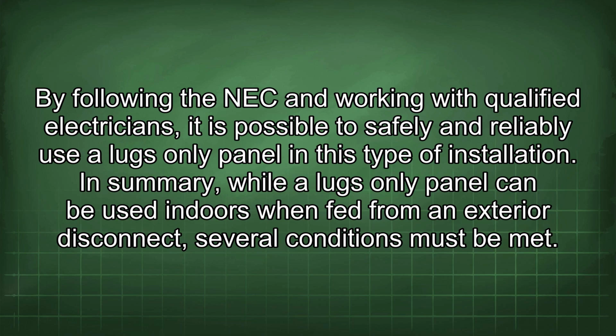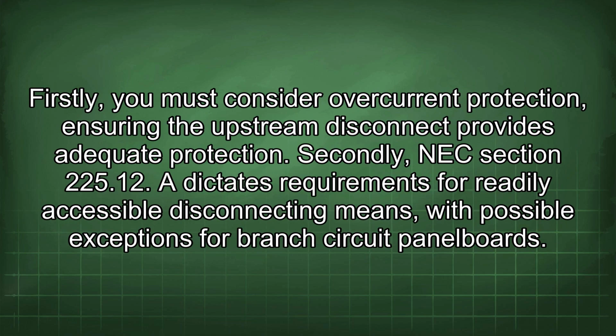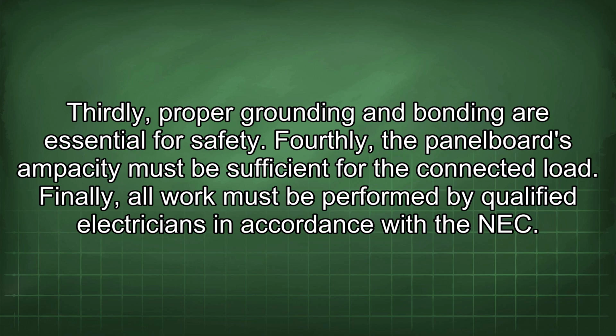In summary, while a lugs-only panel can be used indoors when fed from an exterior disconnect, several conditions must be met. Firstly, you must consider overcurrent protection, ensuring the upstream disconnect provides adequate protection. Secondly, NEC Section 225.12 dictates requirements for readily accessible disconnecting means, with possible exceptions for branch circuit panel boards. Thirdly, proper grounding and bonding are essential for safety. Fourthly, the panel board's ampacity must be sufficient for the connected load. Finally, all work must be performed by qualified electricians in accordance with the NEC.